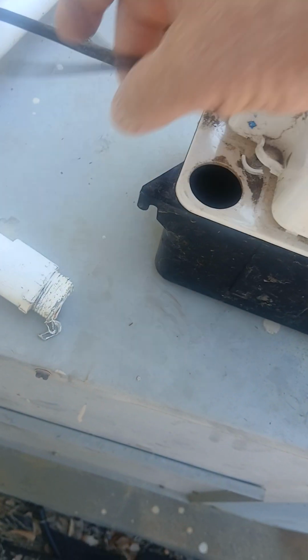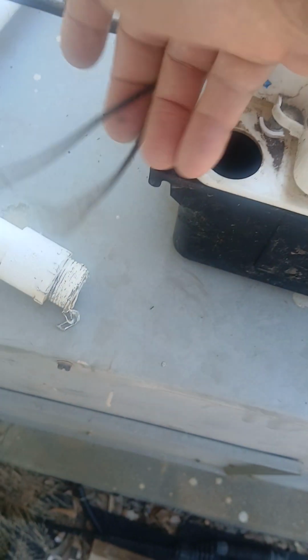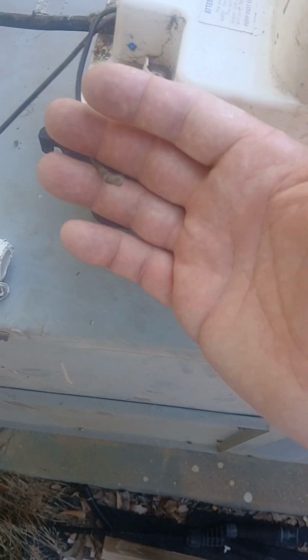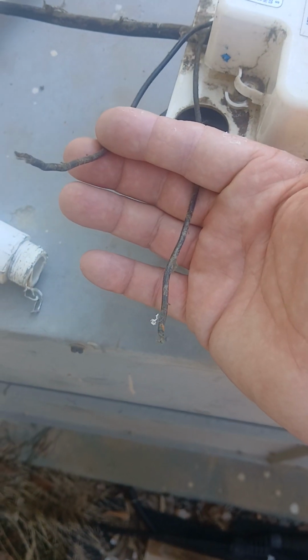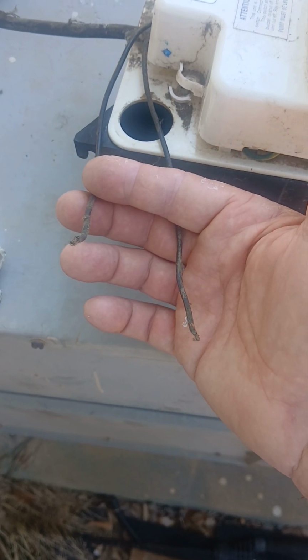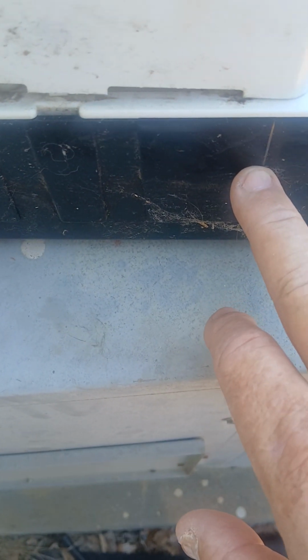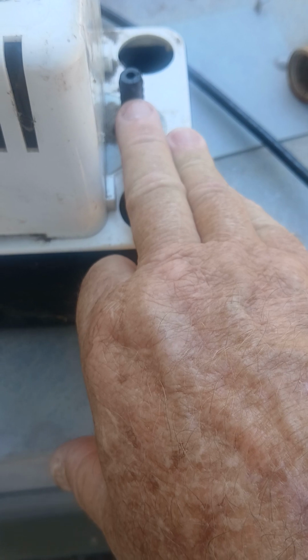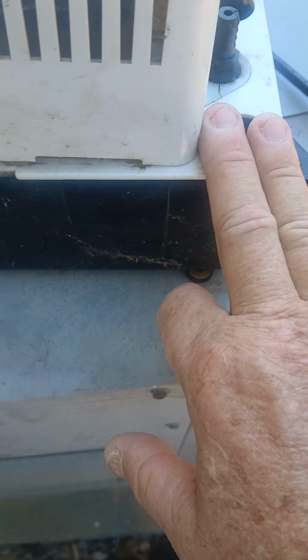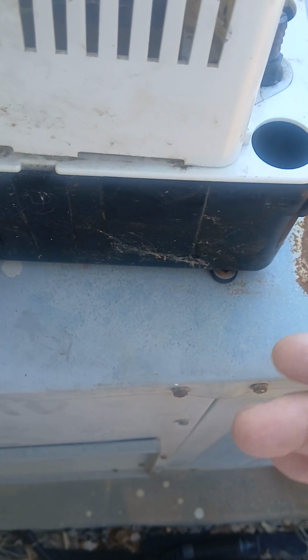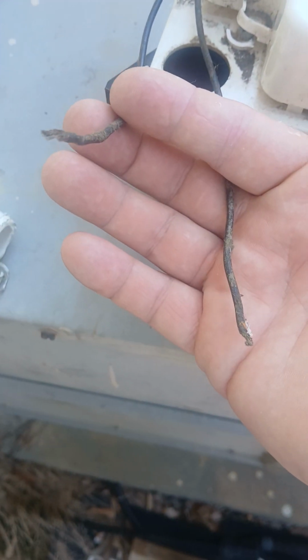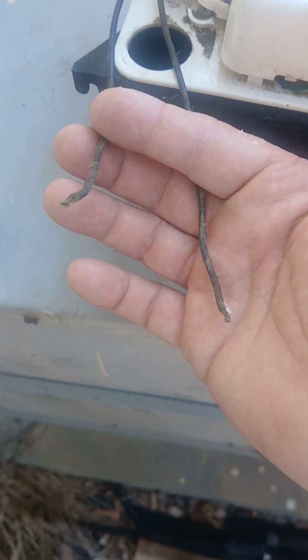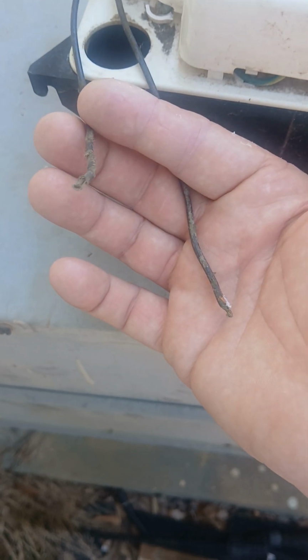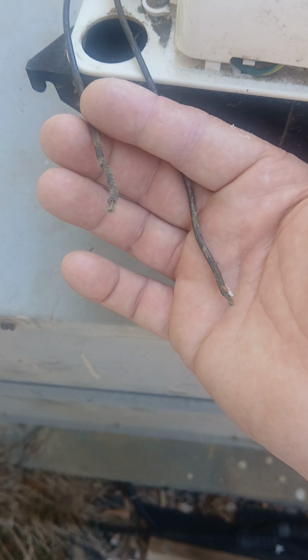But the question and the topic here are these two wires here. We have the big wire, and then we have the two wires, the small wires. Now, one may ask, well, what are these wires for? Now, the HVAC gurus can chime in. I think these wires here, if this bucket or this pan gets full at a certain point, and say hypothetically if this were to get stopped up, once this gets stopped up and the water can't flow, as opposed to the water coming over and cresting over, and the reason one would have a pan, you could hardwire this into the low voltage on your red wire. Now, maybe the HVAC gurus can help me out here. I believe you could wire it in on your yellow wire if your yellow wire goes to the condenser too.